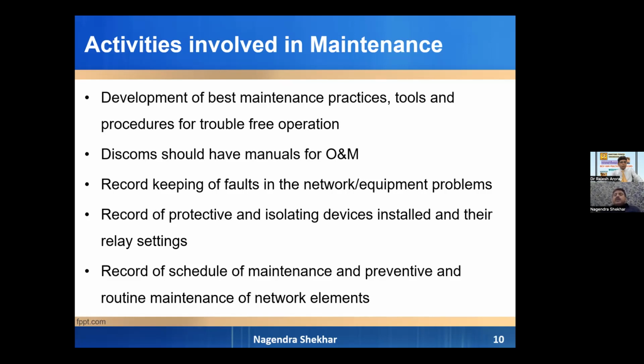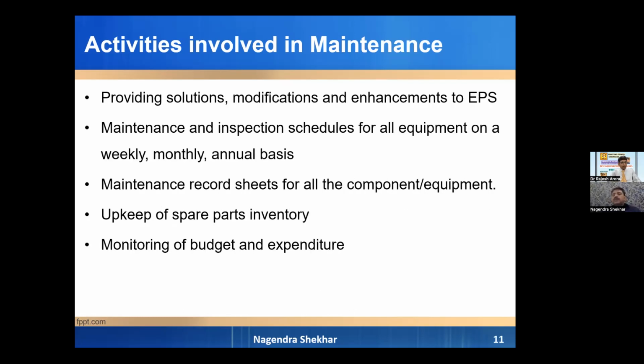Next, we must keep a record of faults so that next time we can understand what the fault was, what the reasons were, and why it has reoccurred or another fault has occurred, so that the life of equipment can be increased. Record of protective and isolating devices installed and their relay settings, basically switchgears. So when it was set at what load and what percentage, what was the time for tripping and fault currents. Scheduled maintenance and preventive maintenance of all the elements of the distribution network must be recorded so that they can be referred to as future references.